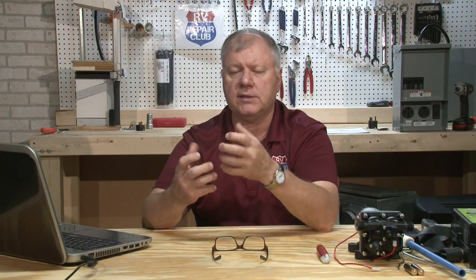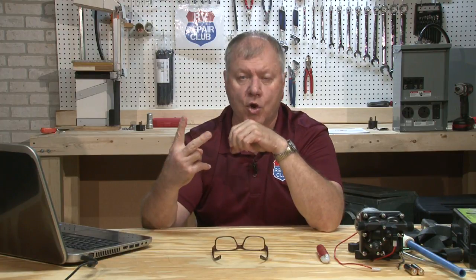Unfortunately, we have local here, we have Surf Ballroom, and every February we have a big celebration for the music and the life of Buddy Holly and Richie Valens. They always bring RVs out there and plug them in for the bands as a green room, and even though they plug into electricity, they don't have 30 amp, 50 amp stuff. They're running low, then they go and plug in a whole bunch of ceramic heaters, all the stuff, and it seems like every year they blow up an outlet and they can't figure out why it's not working. It looks like it works, and you go in and they actually test the outlet with a multimeter. Sure enough, it's not working. Something internally in that GFCI outlet has basically created an open, and I don't...